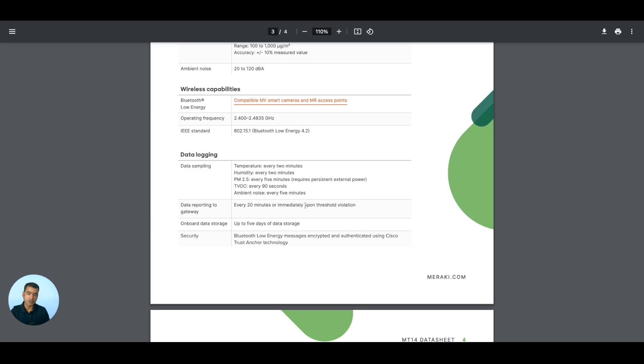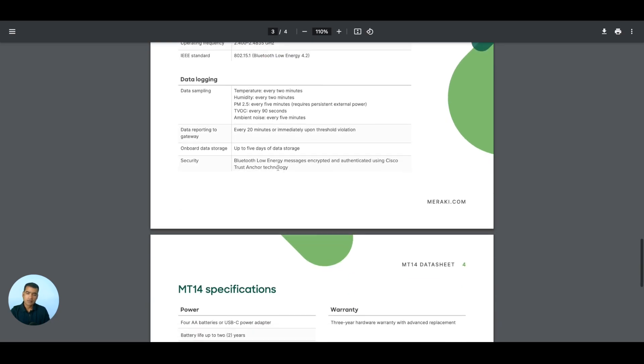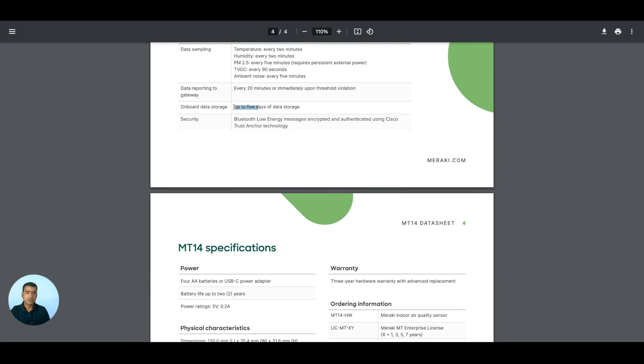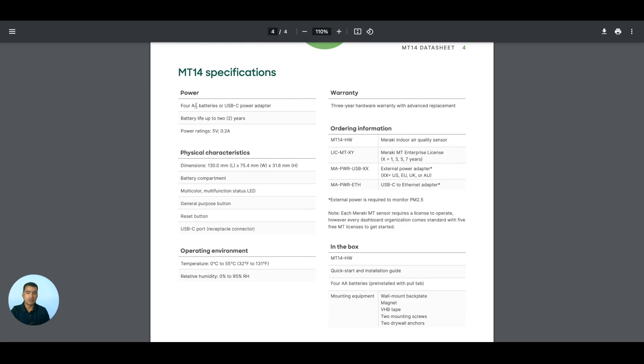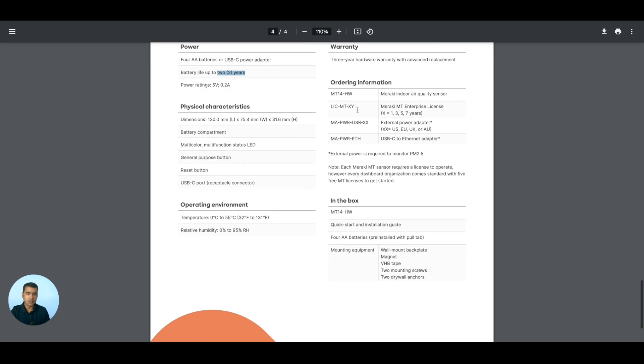Data reporting to the gateway is every 20 minutes. There is also onboard data storage — 5 days of data storage locally. It is secure using Bluetooth Low Energy message encryption and authenticated using Cisco Trust Anchor. Power options: 4 AA batteries or a USB-C power adapter, since the device has a USB-C port. You would use USB-C when you want to monitor PM2.5. Battery life is pretty good.